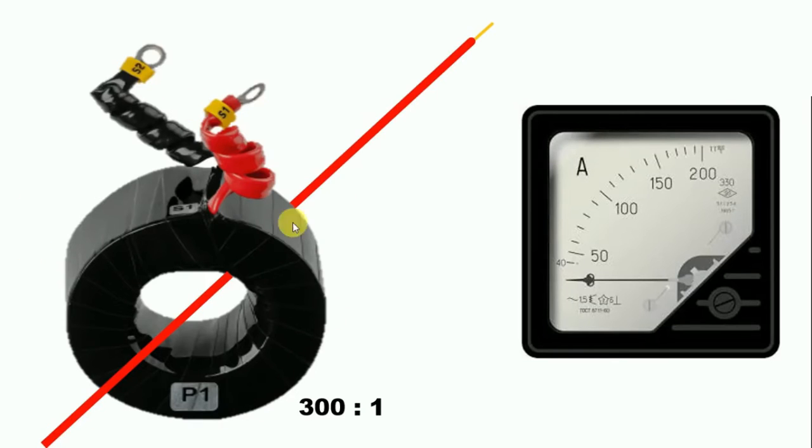Friends, as you know, the ratio we use in CT, we have to use the same ratio in the ammeter also. Like the ratio of this CT here is 300 by 1, so the ratio of the ammeter we use must also be 300 by 1.